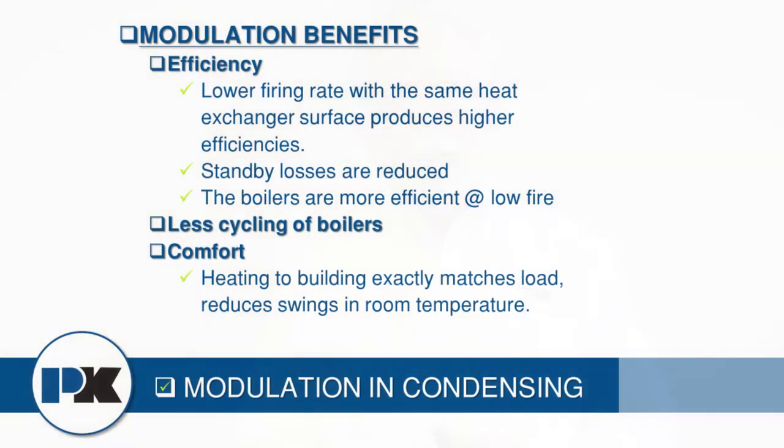This is why at Patterson-Kelley we've decided that 10 to 1 turndown is sufficient. We do it without excess air to maintain our dew point, and we're still at a high enough flow rate to get the mixing that was designed into the heat exchanger in the first place.